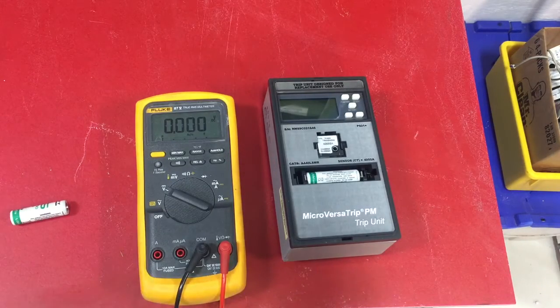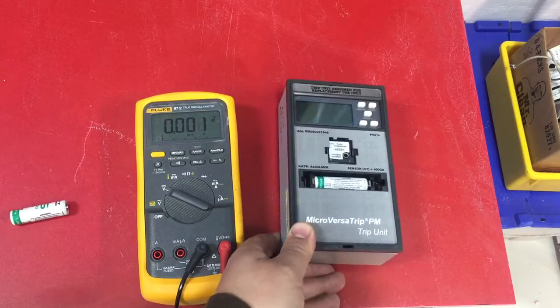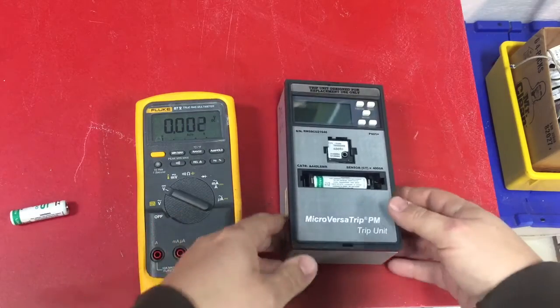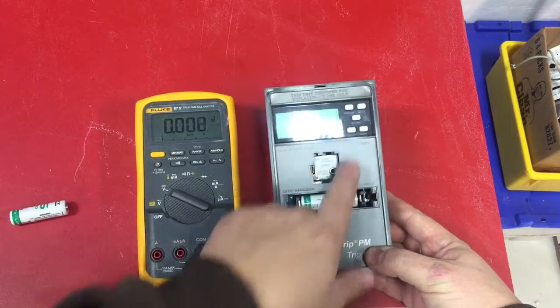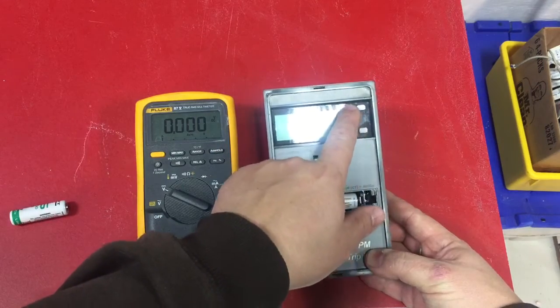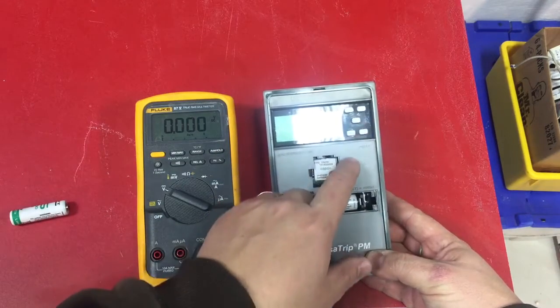Good morning. Here we are with a GE MicroVersaTrip PM trip unit that we just got in. The problem with this one is the display won't come up. If you hit the battery button, the display should come up.